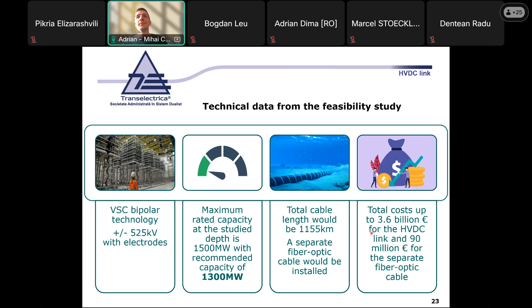The feasibility study contains some technical data. We identified that the feasible technology is VSC bipolar technology, plus/minus 525 kV voltage with electrodes. The maximum capacity is 1,500, but the recommendation would be an installed capacity of 1,300 megawatts. The total cable length is approximately 1,155 kilometers, with a separate fiber optic cable to be installed. The total investment would be up to 3.7 billion, of which 3.6 billion would be for construction of the HVDC link plus converter stations, and almost 100 million for the separate fiber optic cable.